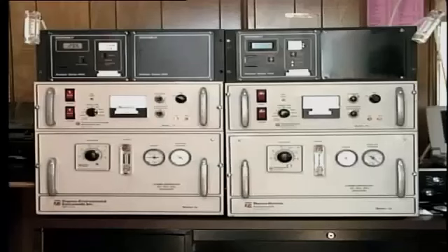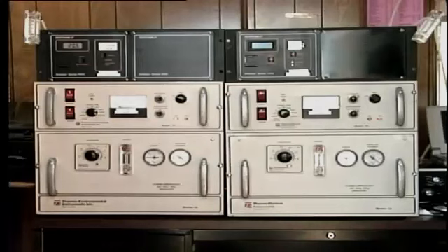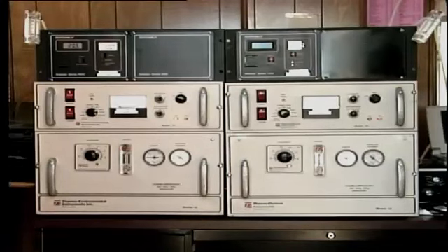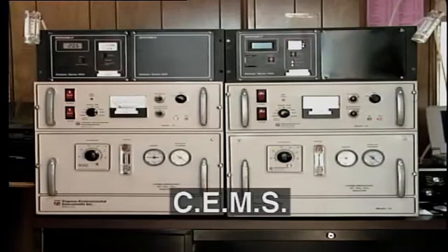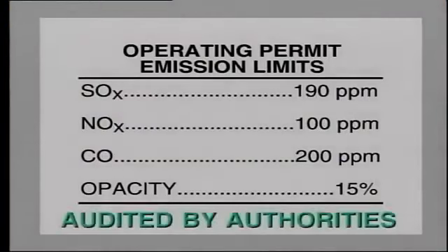Compliance with the environmental regulation is essential in order for the plant to retain its operating license. The operating procedures, equipment design, and maintenance are all developed with these regulations in mind. Monitoring of critical discharges from the plant is performed on a continuous basis through the Continuous Emission Monitoring System, known as CEMS.